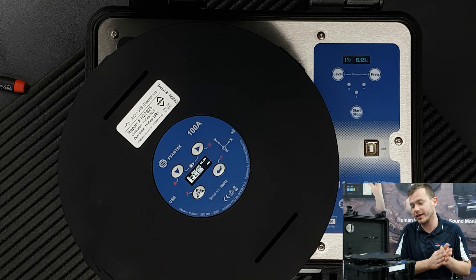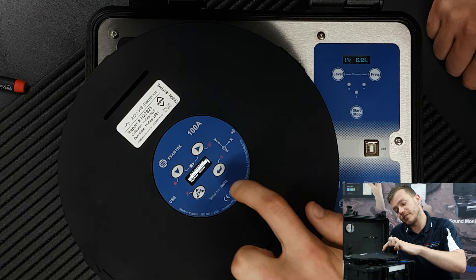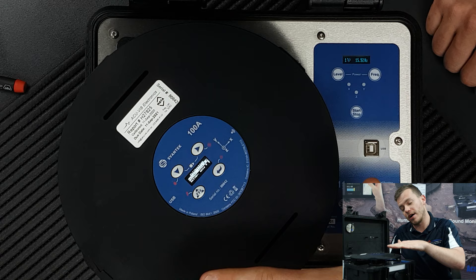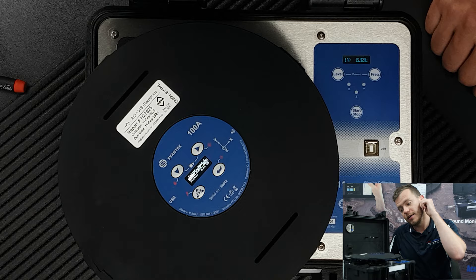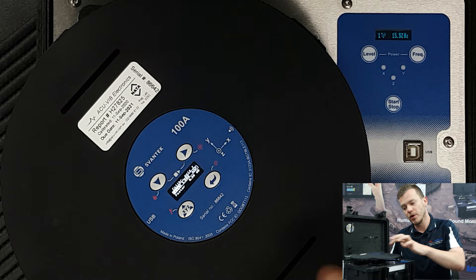For the SV100A there's a calibration button at the top, so we're going to hold the top right button to go into the calibration menu. For this video I'm going to do it by measurement. Because we're doing the Z-axis, which is the vertical axis, I'm going to scroll down until we get to Z and press enter. Our level is 1 meter per second. We press start on the calibration; there's a five second delay that gives me time to press start on the shaker which is going to auto level.